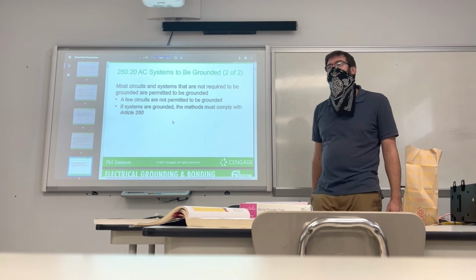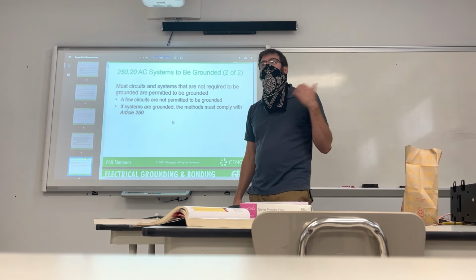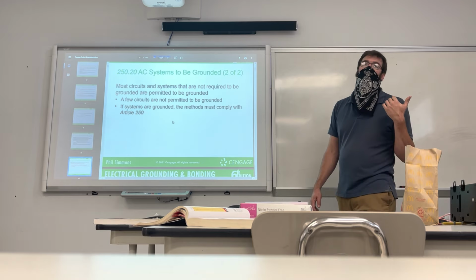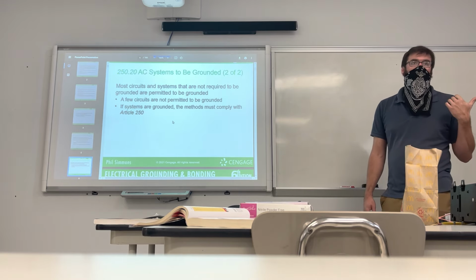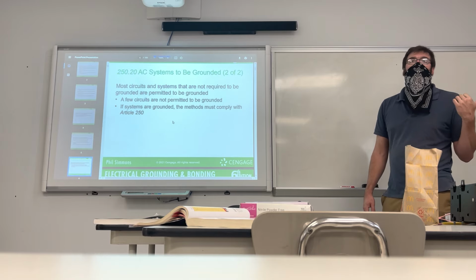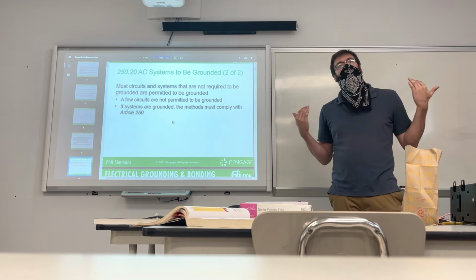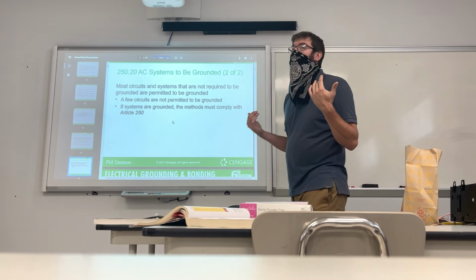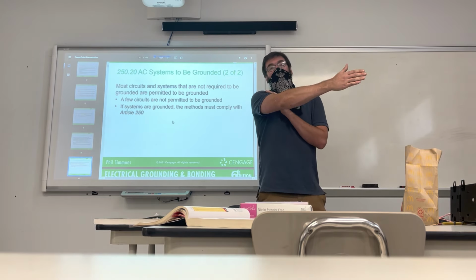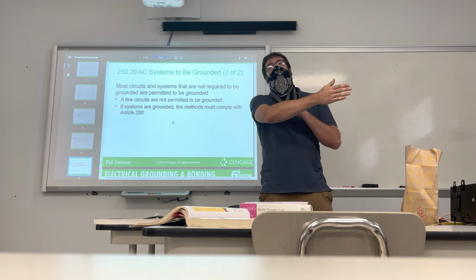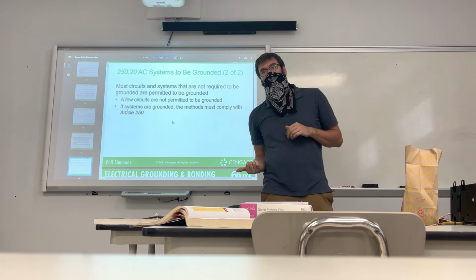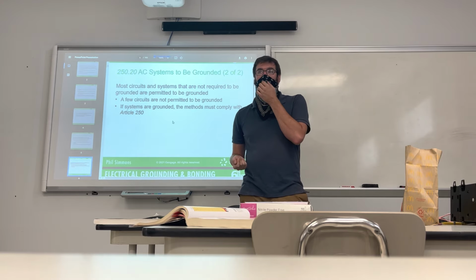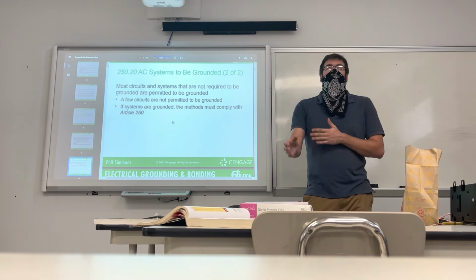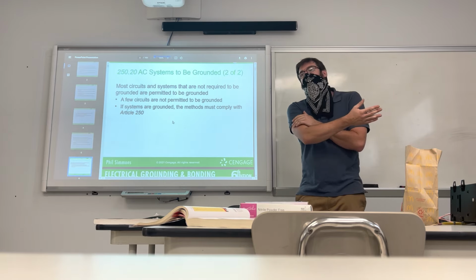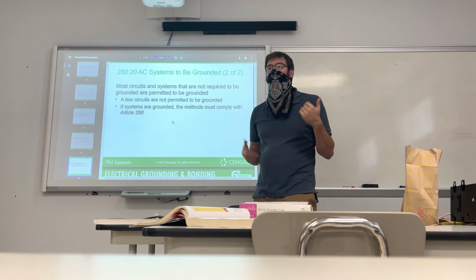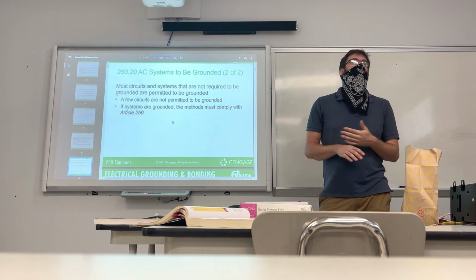Just like if you're in a crane, right? And you're working around high voltage lines that can easily combust. I know that's not often. I know you guys aren't going to be working on a crane every day. But if you're working around things that can easily combust, you want that crane to be non-grounded. Because if that crane is grounded and that crane comes across that wire, that whole crane is now going to be hot and it's going to make that wire explode because it just got its way down to ground. It just shorted out that circuit. If the crane is ungrounded, it can just sit there and be hot. Now that's not good either, but at least you won't have an explosion. So there are a couple instances, but they are few and far between.